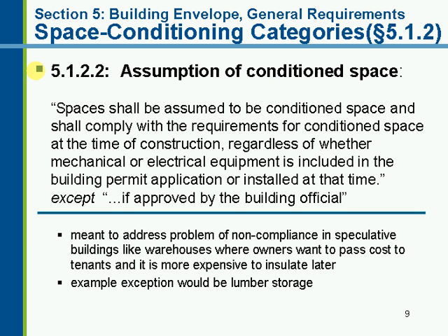because this has been a key compliance problem in the past where owners have built a shell building and then later on a tenant comes forward and the tenant is surprised to find out that, oh, they can't just move right in. They have to insulate the walls and insulate the roof. And it's obviously much more cost effective for a warehouse, for example, to insulate the roof when you're constructing it. You've got maybe a 20, 24-foot ceiling, you've got scaffolding or whatever the system is you've got set up to install the structure. The thought of coming back later on and trying to insulate that would be a much more costly situation. So those are things that need to be taken care of right away.